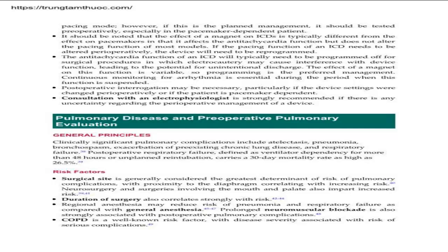It should be noted that the effect of a magnet on ICDs is typically different from the effect on pacemakers in that it affects the antitachycardia function but does not alter the pacing function of most models. If the pacing function of an ICD needs to be altered perioperatively, the device will need to be reprogrammed.